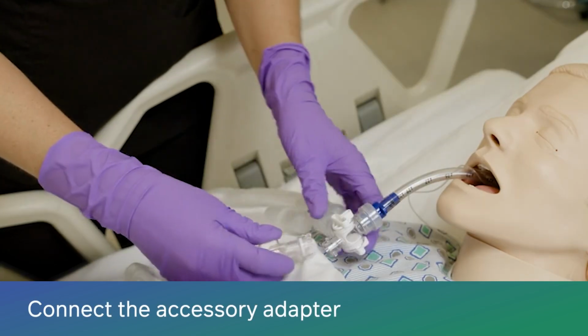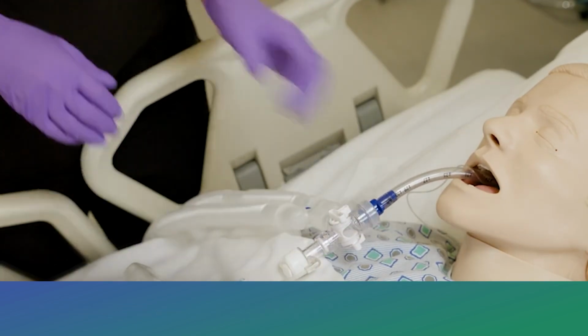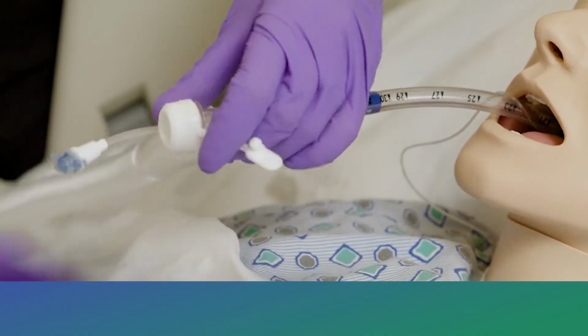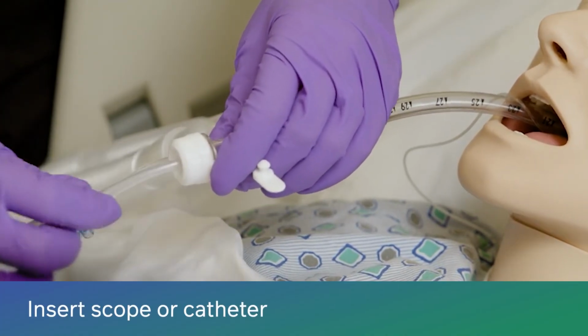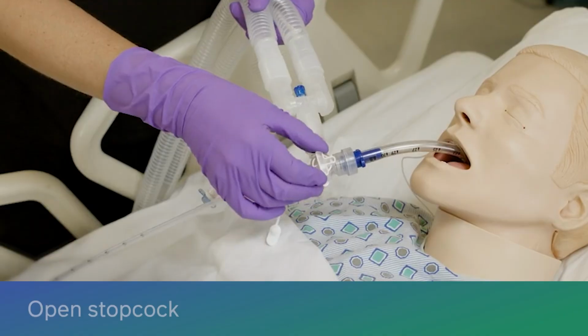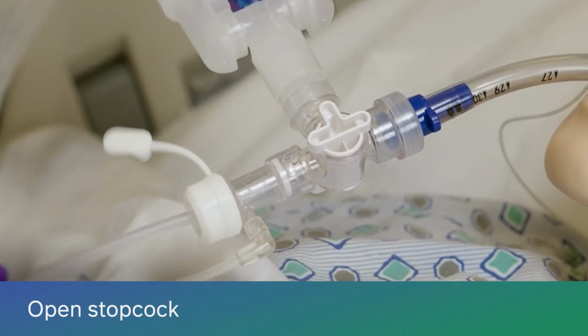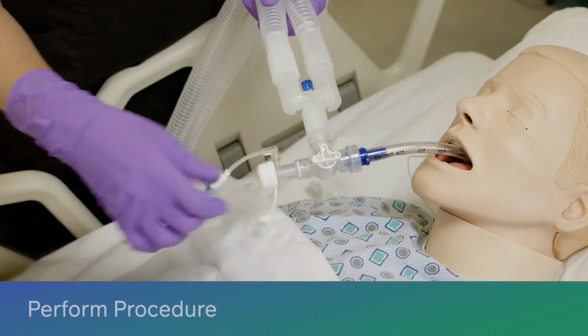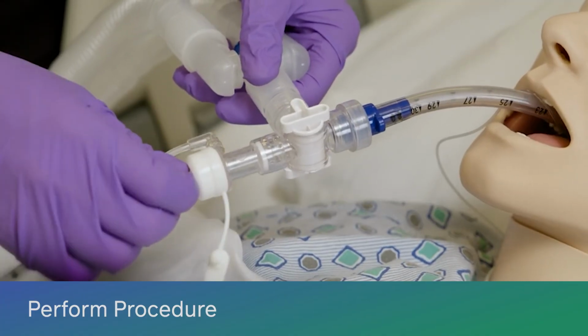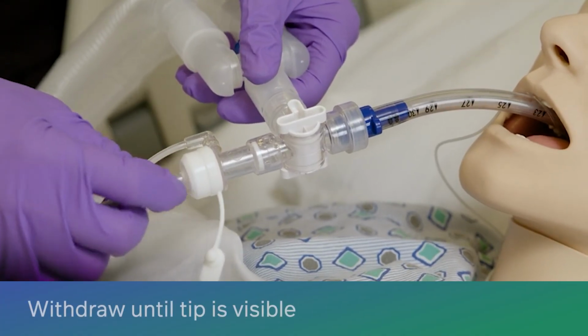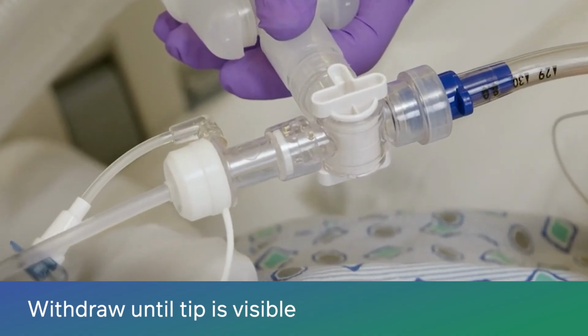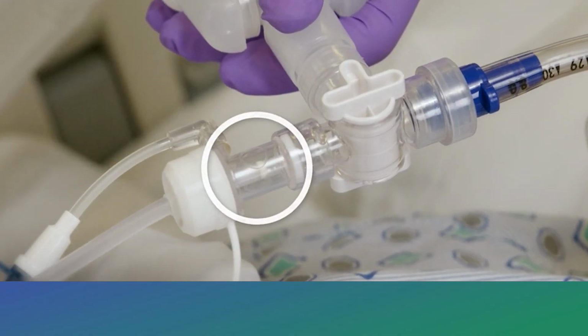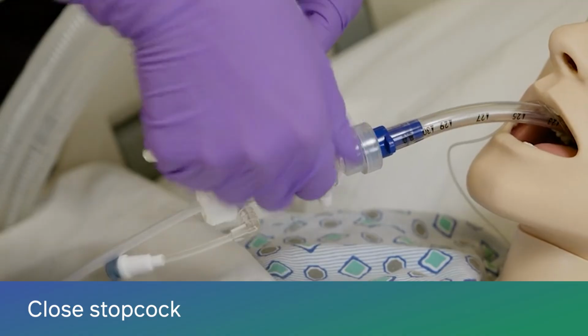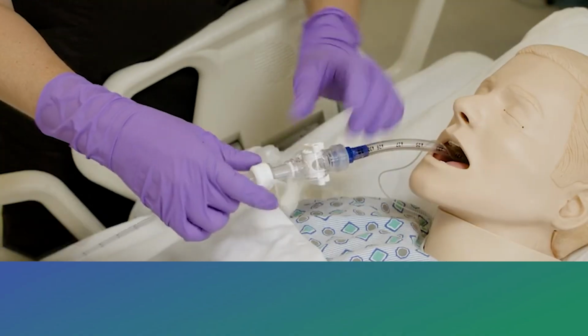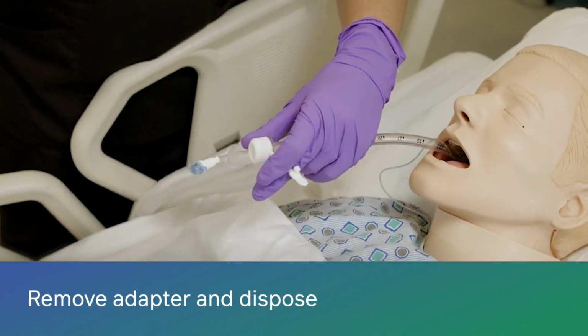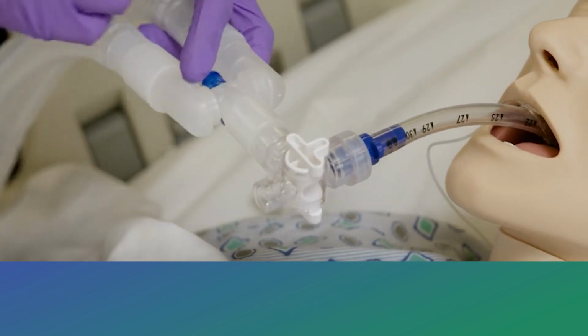Carefully connect the accessory adapter to the manifold by twisting. Open the cap on the adapter, insert bronchoscope or mini BAL catheter into the accessory adapter, and then rotate the stopcock to open the manifold to the device. Advance the bronchoscope or BAL catheter as needed and perform the procedure. Once the procedure is complete, withdraw the device until the tip is visible proximal to the stopcock, and then rotate the stopcock back to ventilator-only position. You may now remove the device from the adapter, disconnect the adapter from the manifold and dispose of it properly.